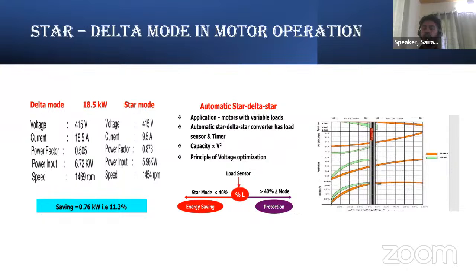There will be a load sensor placed here. If the load gets less than 40%, then the star mode will be activated. If it goes beyond the 40%, then delta mode will be activated. In the right side graph, you could see in the star delta connection, the power factor is getting affected with respect to the loading pattern. You could see that in the graph.